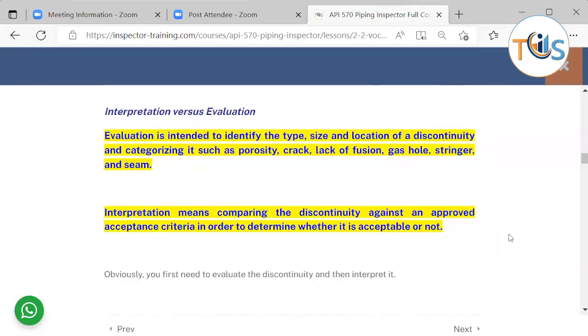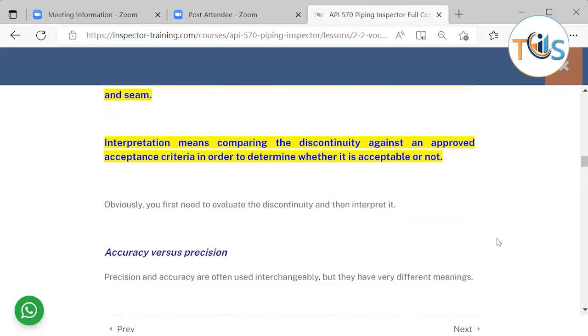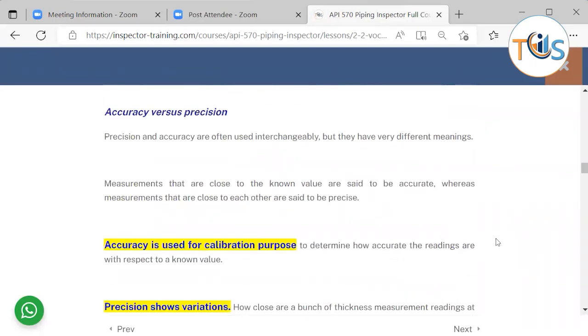Evaluation is intended to identify the type, size, and location of a discontinuity and to categorize it — such as porosity, crack, lack of fusion, gas hole, stringer, and the like. Interpretation, on the other hand, means comparing the discontinuity against an approved acceptance criteria in order to determine whether it is acceptable or not. You first need to evaluate the discontinuity and then interpret it.